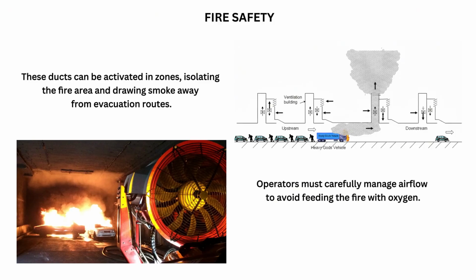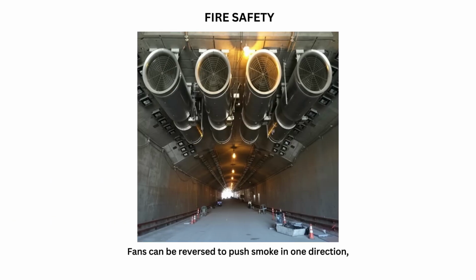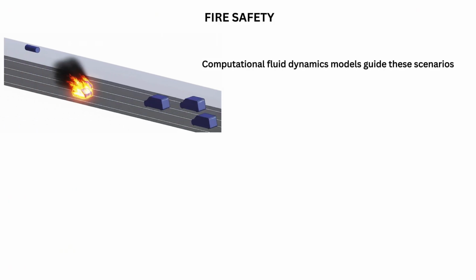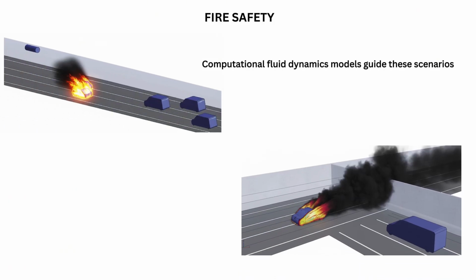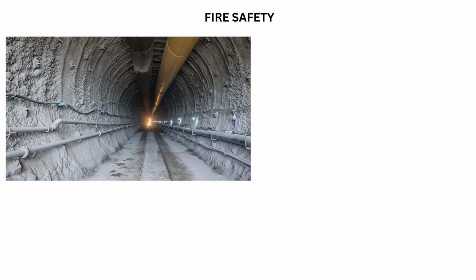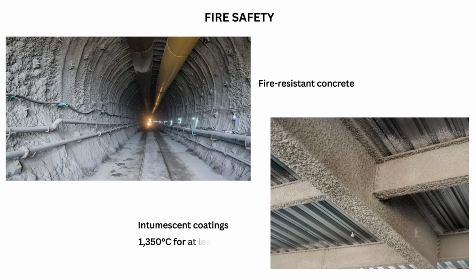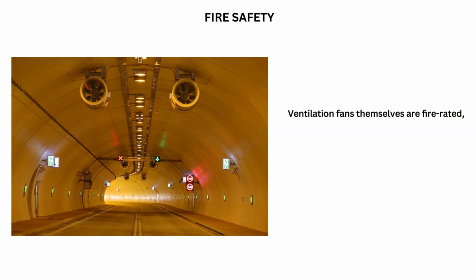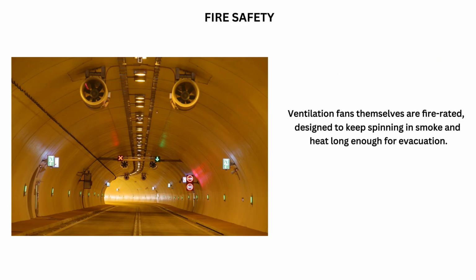Operators must carefully manage airflow to avoid feeding the fire with oxygen. Fans can be reversed to push smoke in one direction, always away from evacuees. Computational fluid dynamics models guide these scenarios, simulating different fire loads and vehicle positions. Tunnel linings are protected with fire-resistant concrete or intumescent coatings that can withstand 1,350 degrees Celsius for at least 2 hours. Ventilation fans themselves are fire-rated, designed to keep spinning in smoke and heat long enough for evacuation.